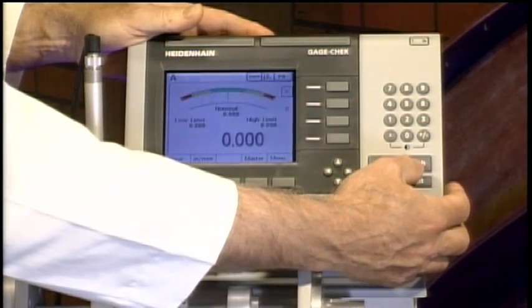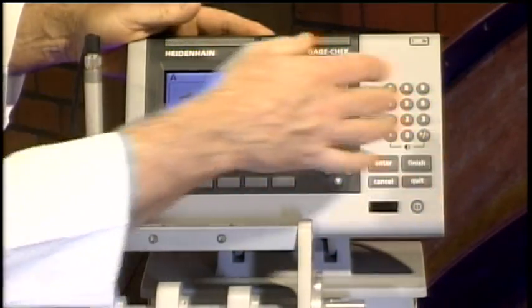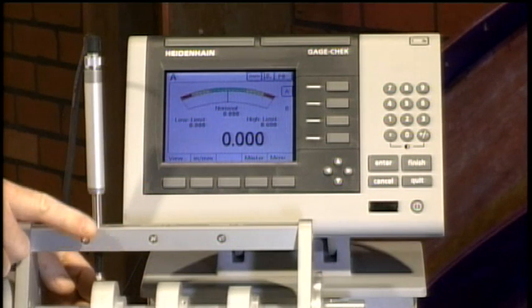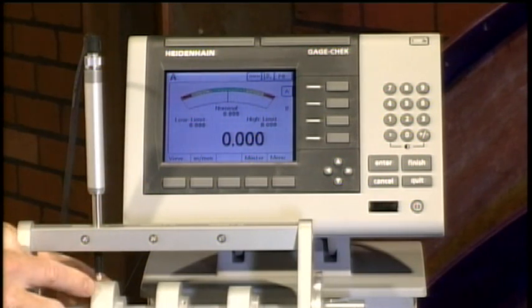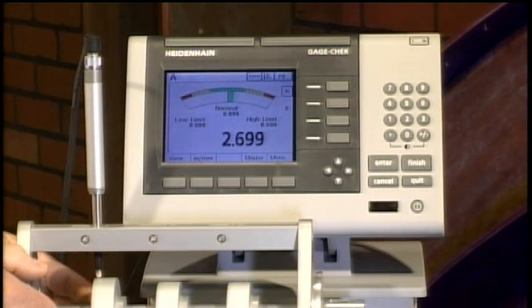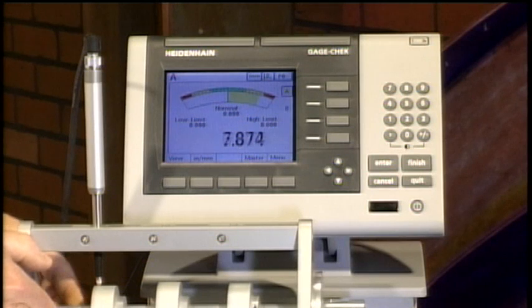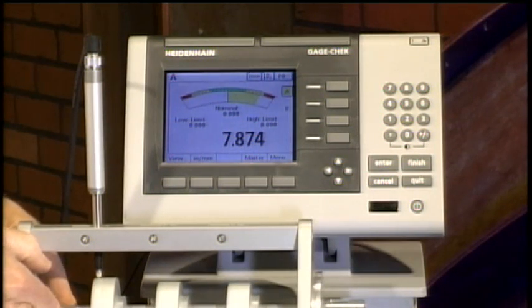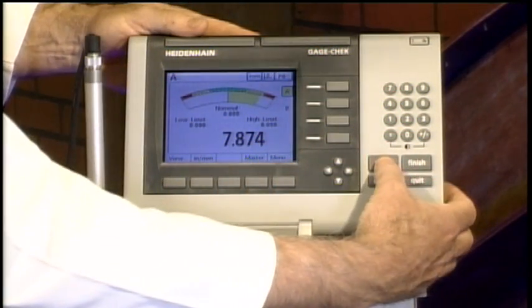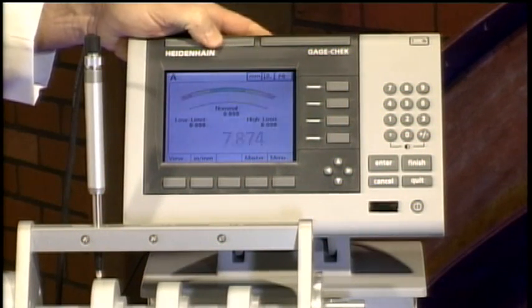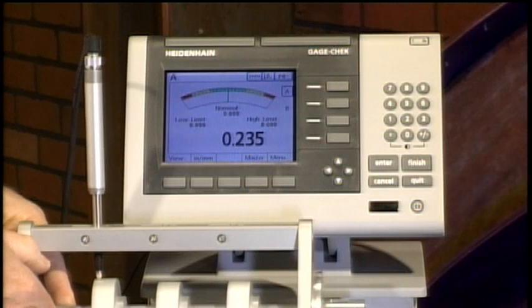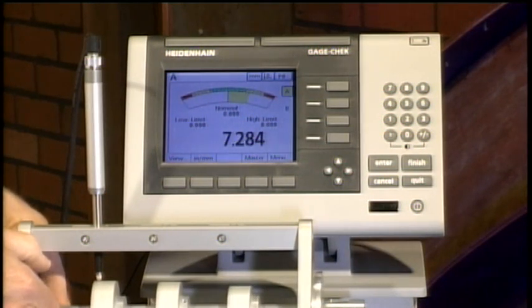So now I can simply go back to my display, and we're looking at A. I've got a little test fixture here. You can see here's my linear measurement gauge right here. I've got a little cam on the bottom. As I rotate this, you can see the gauge move up and down. If you look at the value, you can see my value is slowly increasing as it finds the maximum difference between the high value and the low value. Once I've rotated through 360 degrees, I have simulated my run out there. Now I'll simply store that value, and we'll zero it, and we can take another measurement. We'll do the same thing again. Here again, I'm just rotating 360 degrees. It is calculating for me, on the formula I put in there, what my run out is. So now I can enter that value.